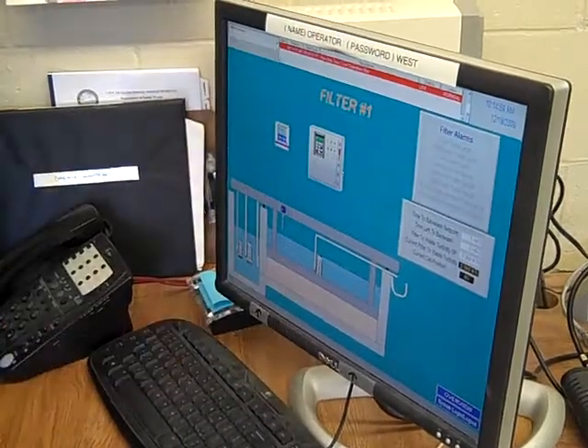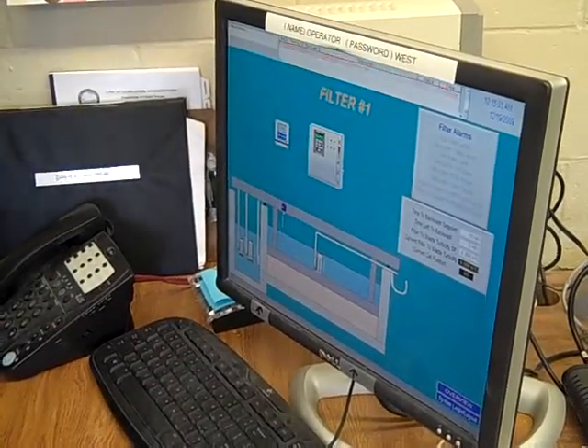There are 80, plus or minus, cells within each filter itself, so you know where your bridge is. So if it stops, you can see it stopped at cell 45. So you know for some reason it stopped in the middle of the cycle. So you can run a diagnostic to figure out why filter 1 stopped. But by having this here, we can tie it into other things.